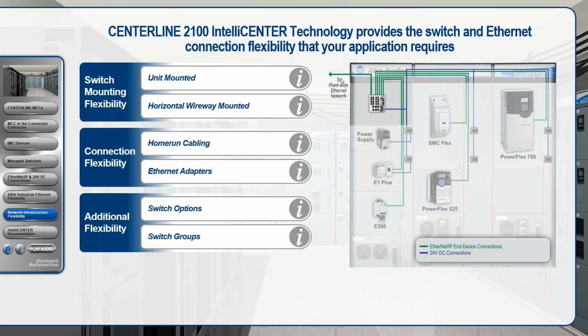We understand that might not always be ideal, and it's very dependent on the case, so it's inappropriate for us to say we have a one-size-fits-all solution. That's why we found that unit-mounted plus horizontal wireway-mounted capability of switch mounting flexibility was appropriate here. With a switch in the horizontal wireway, you can really maximize the space you have in subsequent sections, depending on your bucket configuration or how large your frame or number drive is within that area.